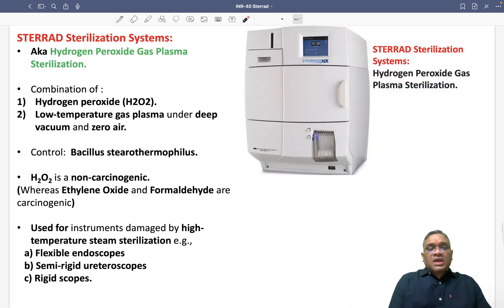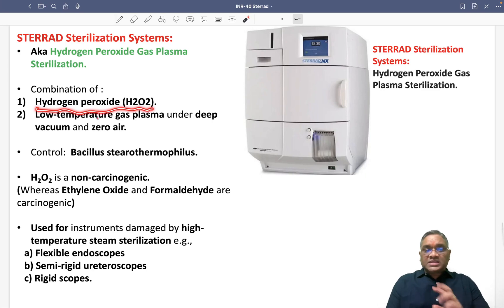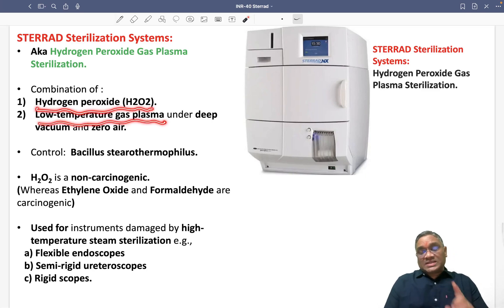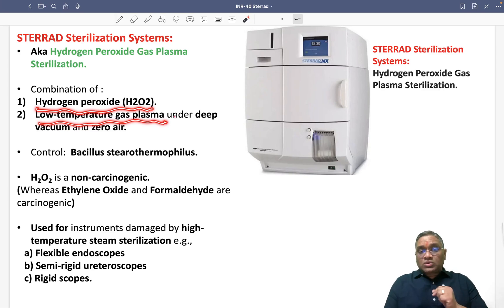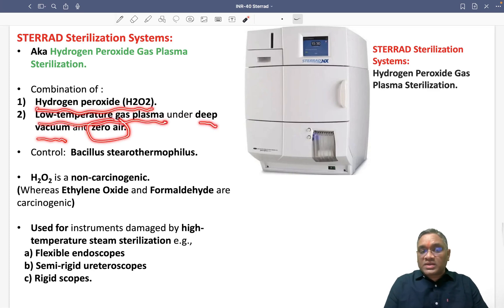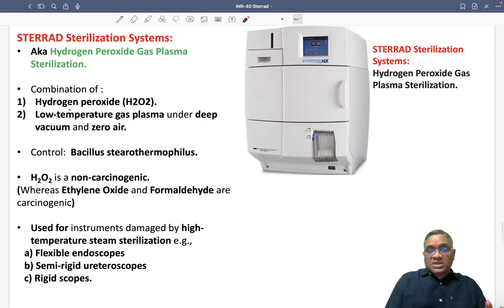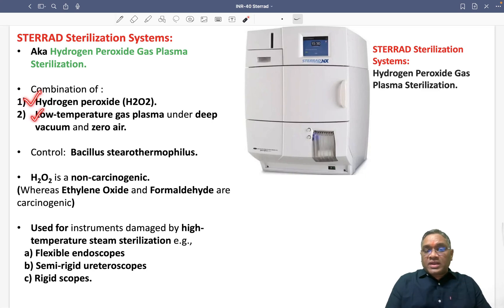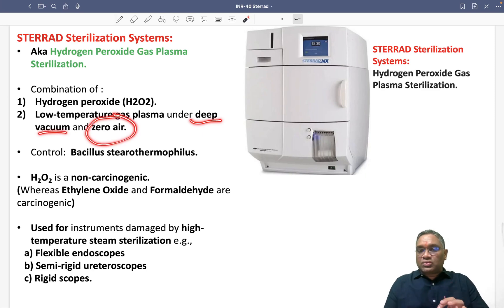So what does it contain? It is a combination of two things: Hydrogen Peroxide plus low temperature gas plasma. Remember, the low temperature gas plasma is also under vacuum — it is under deep vacuum. And the most important thing, there will be no air — zero air. So this Sterrad Sterilization System consists of Hydrogen Peroxide, low temperature gas plasma under deep vacuum, and without air or zero air.